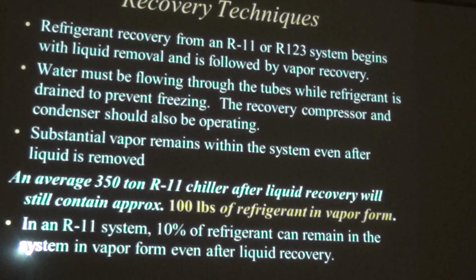Recovery techniques. Refrigerant recovery using R11 or R123 refrigerant systems begins with liquid removal followed by vapor. No matter what kind of refrigerant you're talking about, when you get a test question, it's always you finish as a vapor, no matter which way you go. Water must be flowing through the tubes while refrigerant is drained to prevent freezing. The recovery compressor and condenser should also be operating. Substantial vapor remains within the system even after all liquid is removed.